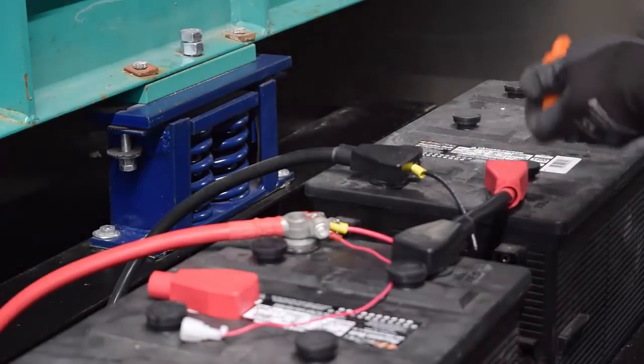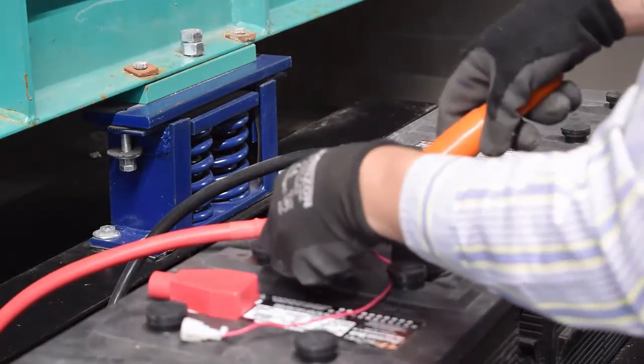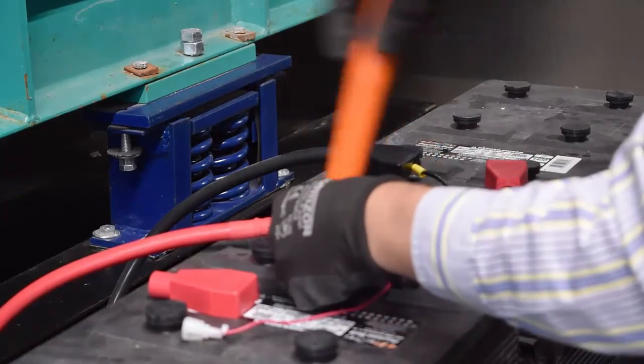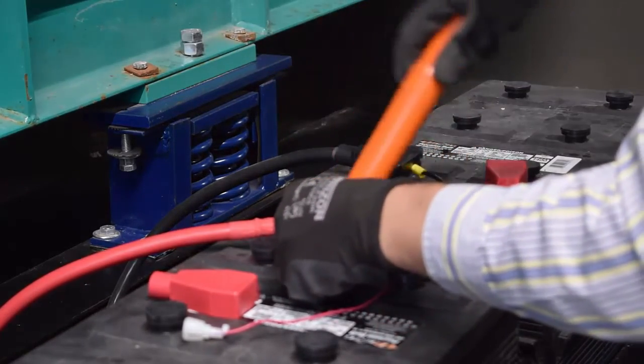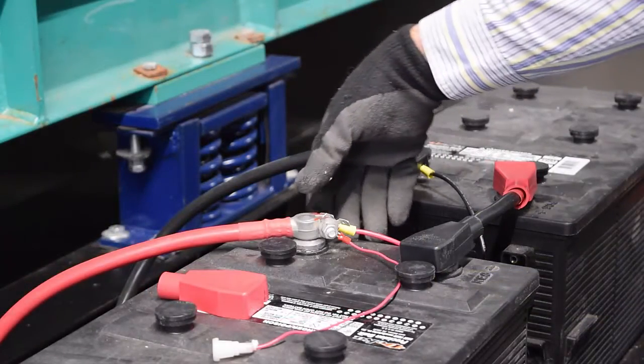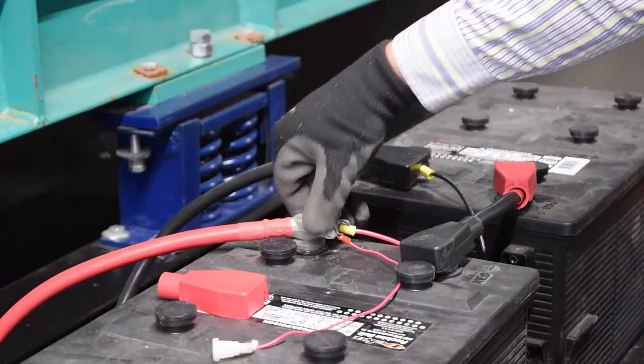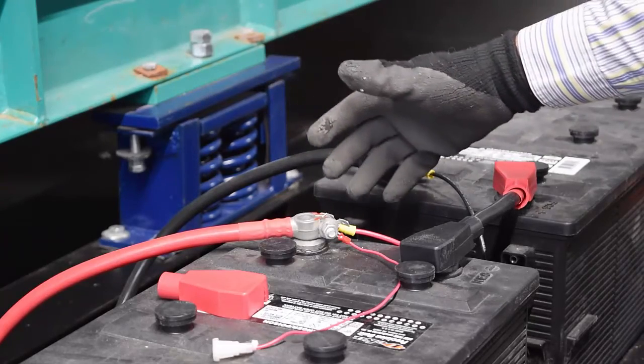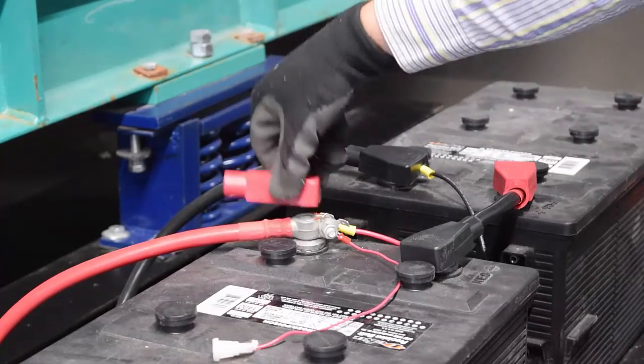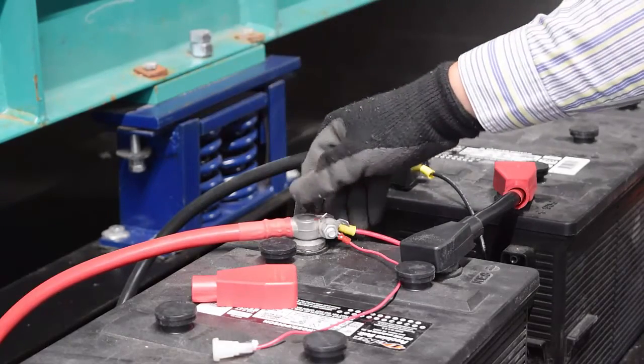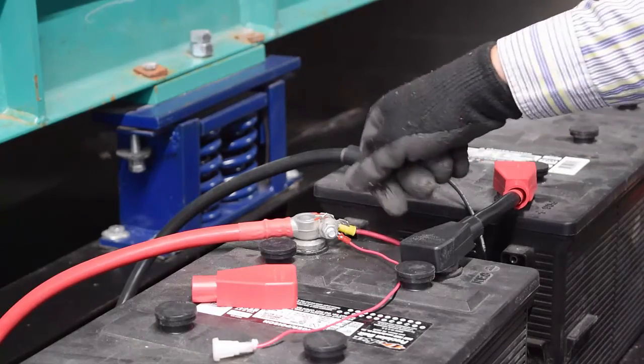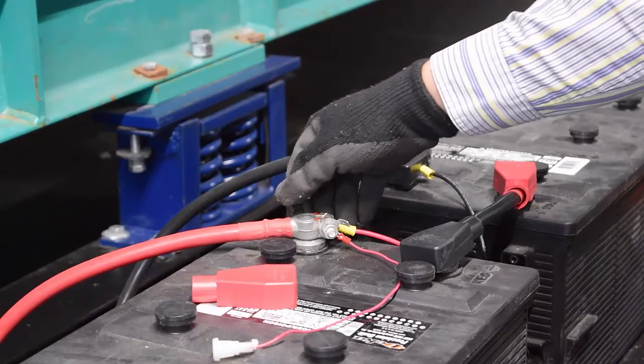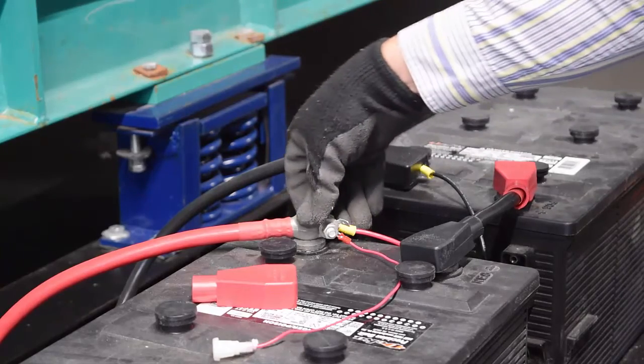Use the insulated torque wrench and tighten the battery terminals to the torque value recommended by the battery manufacturer. Be careful, over-tightening the battery terminals may strip and damage them. So in some cases, you might need to flatten the washers so they do not press against a plexiglass safety shield, or they're out of the way of the safety boot, because if they stick out too far, then the safety equipment is not going to work the proper way, and it's going to be very hard to take the quick disconnects in and out when you need to. So you can do that.